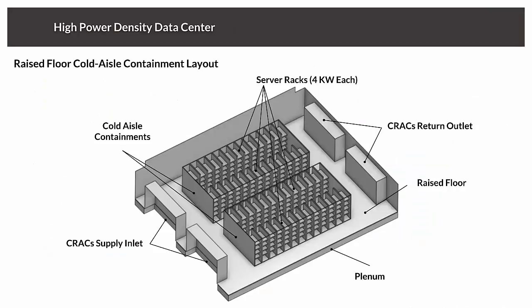Today, we'll look at a general example of a data center that is composed of 4 rows of server racks, 13 racks each, arranged into 4 columns and 4 rows, in a configuration called the cold aisle configuration, where the CRAC units will be introducing cold air through the plenum under the raised floor, and this cold air will be entering an enclosed space between the server rows and later be heated up by the servers and exposed to the external part where the returns will be sucking the air back into the CRAC units.